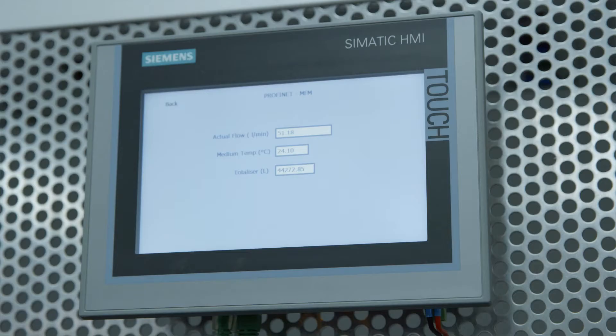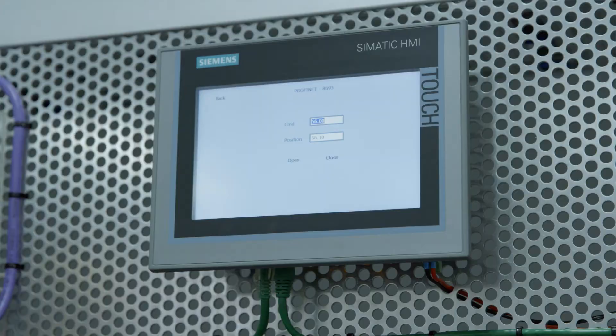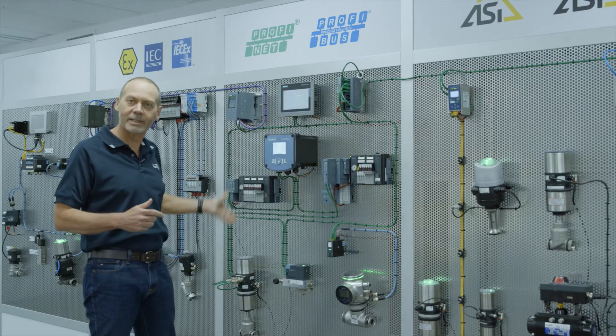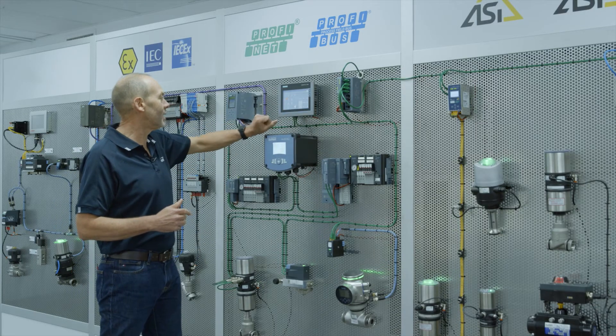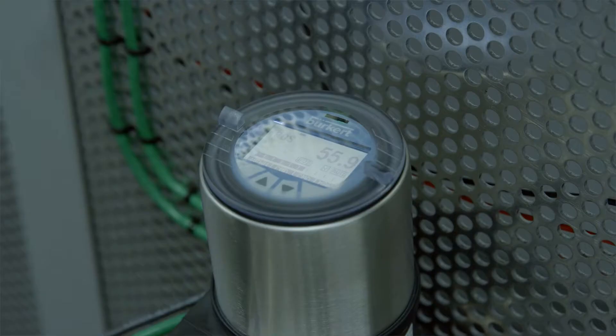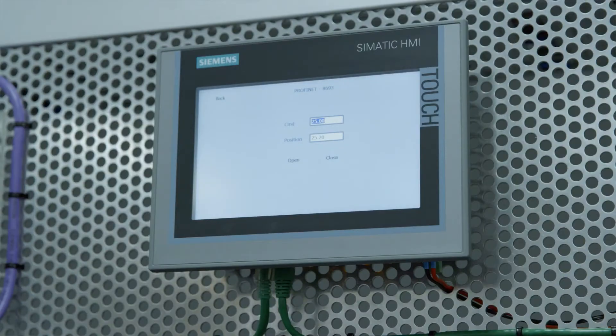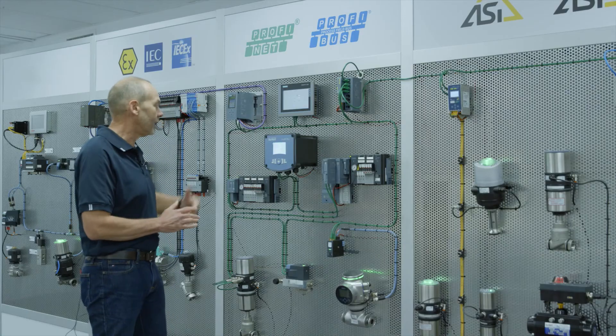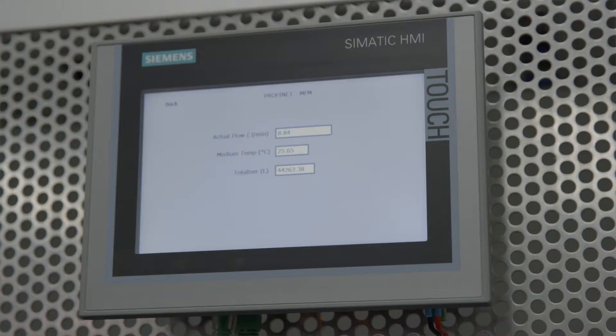I can adjust that down until it goes closed. And the same on a modulating valve — I can connect to this 8693 here and let's change the set point from 56 to 25%. I hit enter, it changes to 25% and I get my feedback telling me it's at 25.2% within seconds. The connectivity is totally seamless to the Siemens system.